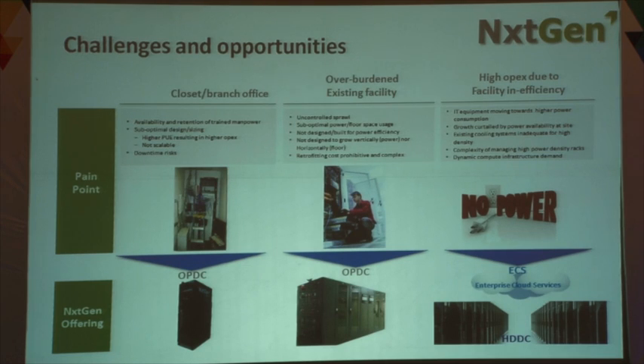This is with a prime focus client where they do digitization work for Star TV and BCCI. The entire data center is built on the same in-row cooling technology with an 80 rack facility. The PUE they get, even with 30-40% utilization of their data center, is 1.6 - that's the kind of efficiency achievable even with low utilization.